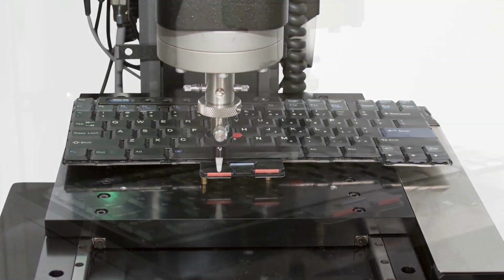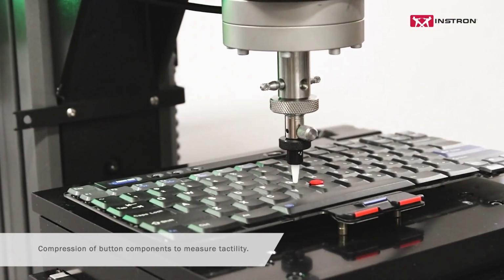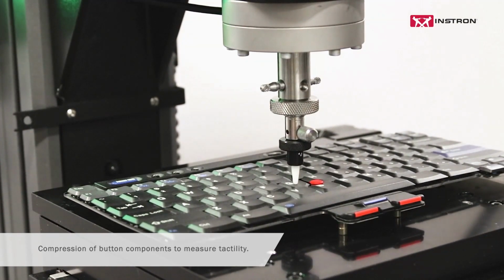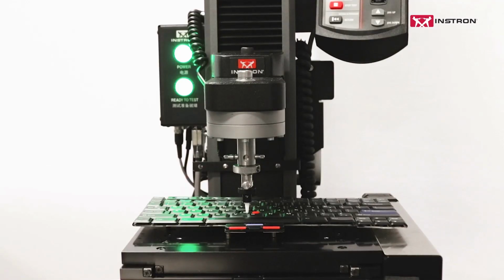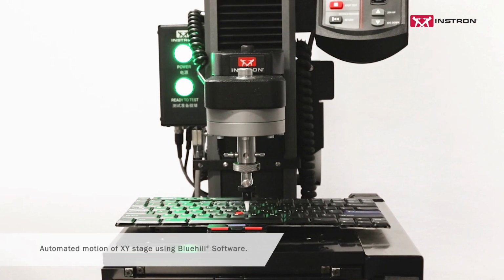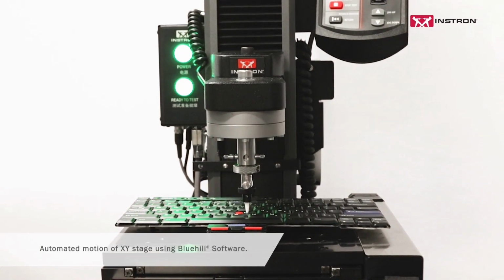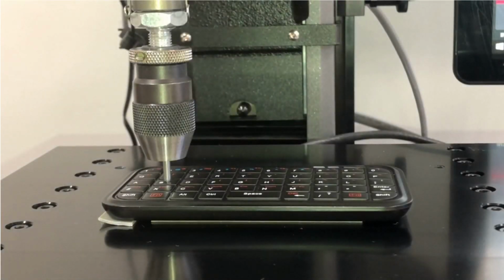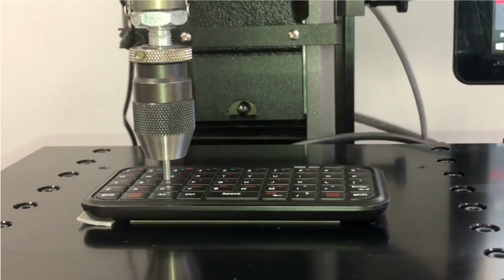XY stages are often used to measure tactility on keyboards. These results can help the product design teams achieve the feel that consumers want in their products. We refer to the collection of test points here that you see the test going through as a sequence. This sequence is created and stored in a software test method. In this video here, we see that mini USB keyboard under test.